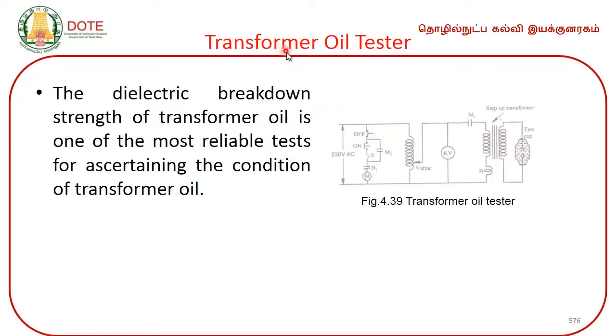Then comes the transformer oil tester. The dielectric breakdown strength of the transformer oil is one of the most reliable tests for ascertaining the condition of the transformer oil. So, this particular transformer oil test kit is employed to find out the strength, that is the dielectric breakdown strength of the transformer oil.